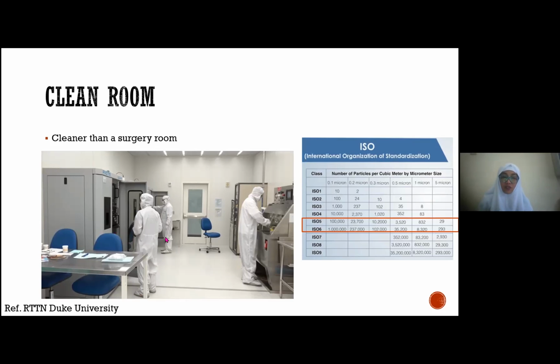As I mentioned before, in the clean room we maintain fewer particles. We have a standard, the International Organization for Standardization, ISO we call it. Mostly we have classes ISO 1 up to ISO 9, showing the number of particles per cubic meter by micrometer size. In ISO 7 up to 9, you can expect at least 0.5 micron particles in large numbers, and when it is 5 microns, the number gets smaller. I think ISO 9 is maybe our normal environment, with a lot of 0.5 micron particles.